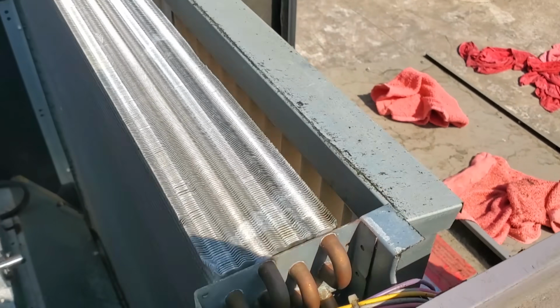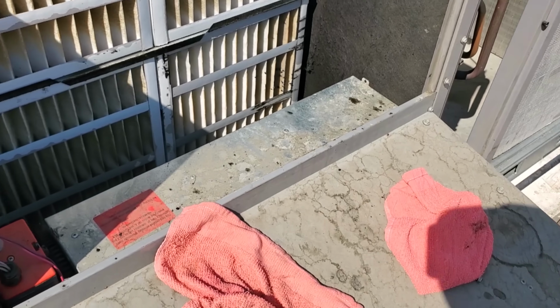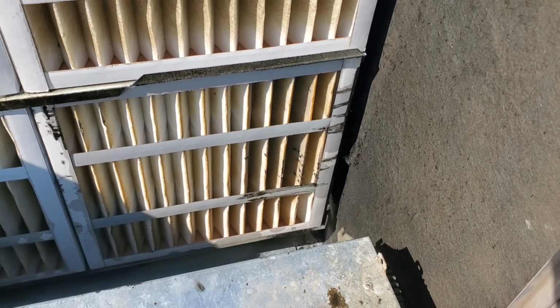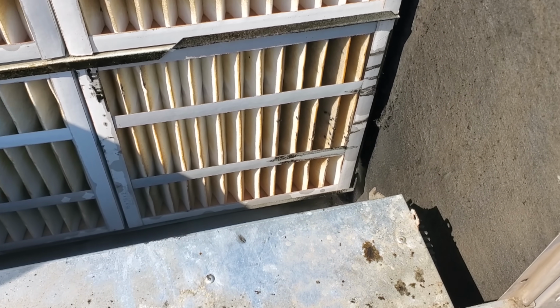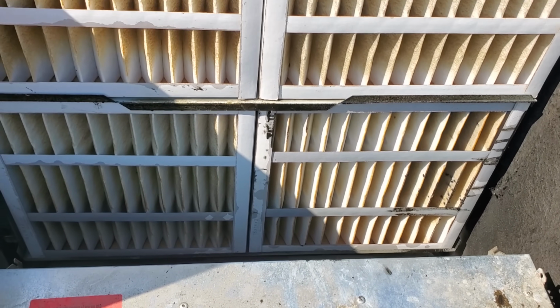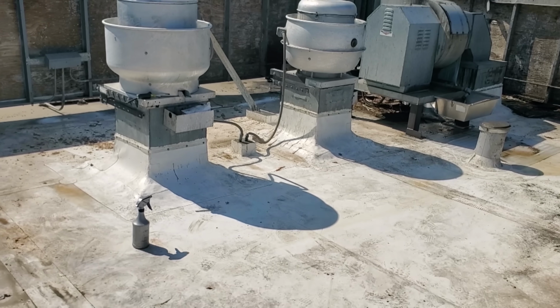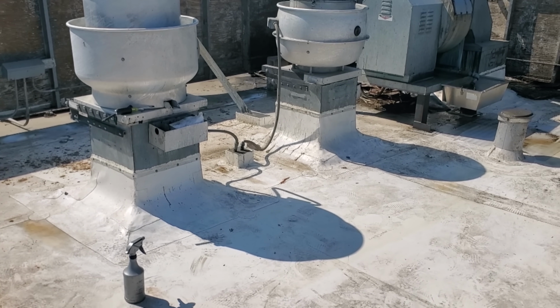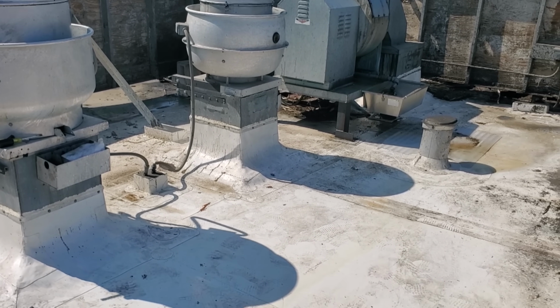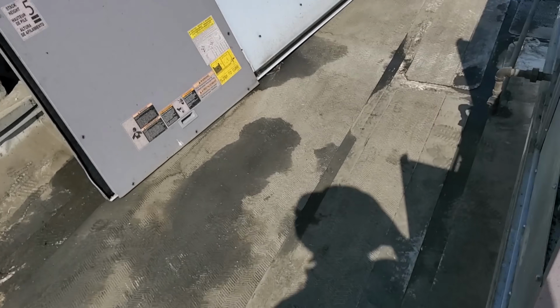But the drain's clear, coil's clean. Those filters too, when we pulled them out they looked wet and we couldn't figure it out - no, that's grease, that's so dangerous. This is nuts. All their exhaust fans are working, but they recently remodeled their kitchen and moved equipment around, and they're probably getting stuff coming right out of the hood.